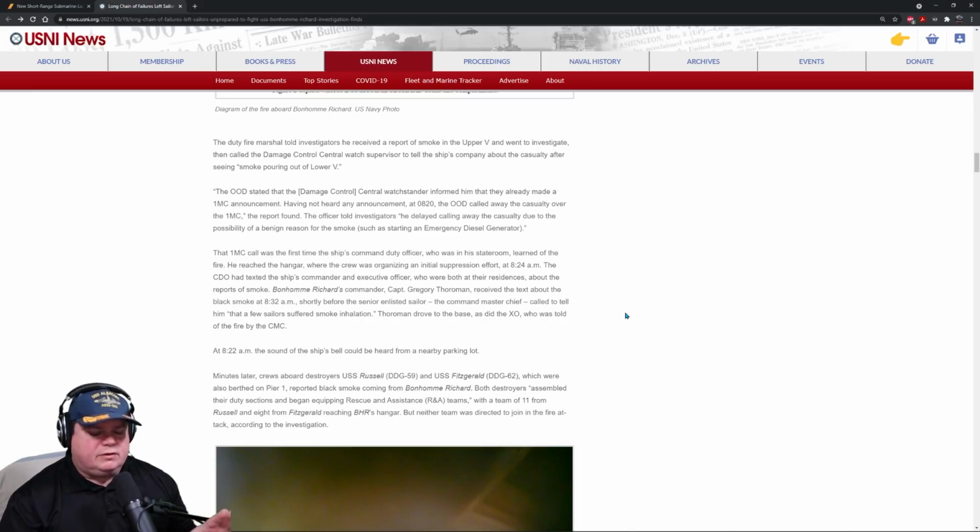So it is possible, especially in this maintenance period, that some of the MC boxes may not be operating. The way this works in shipyards is anytime they take down a communication circuit, like 1MC or 4MC, they'll put in additional communication boxes at key locations where, if there's a casualty, you go to that location, this temporary install, basically, to make the announcement. It sounds like it's either not on board or nobody knows about it, because everyone's trying to use the 1MC or the 4MC. Either one would be the correct one to use. But apparently it's not being announced everywhere. That's adding to lots of the confusion.